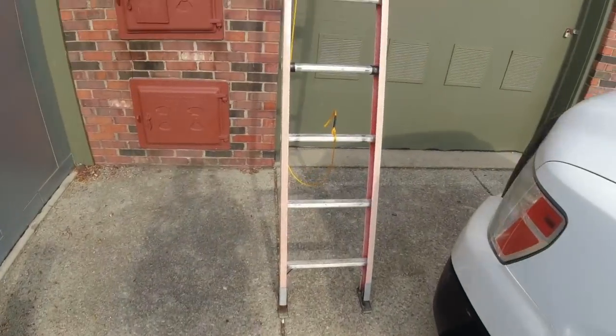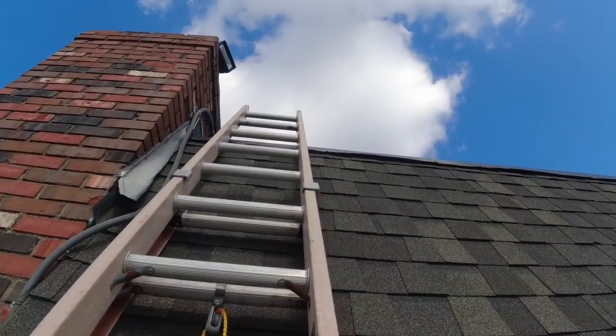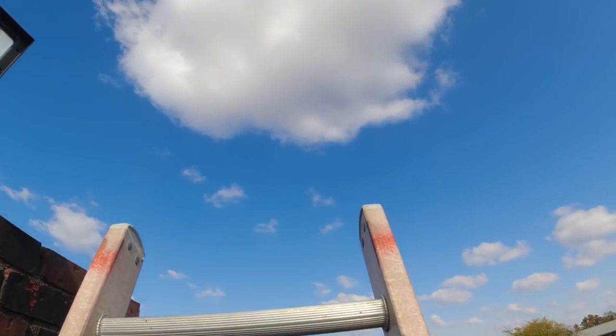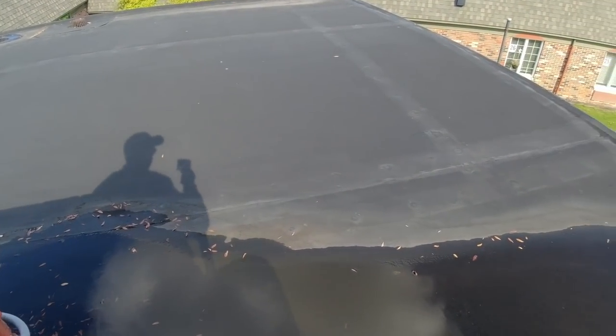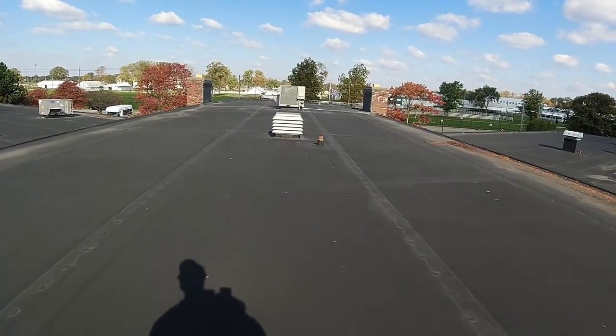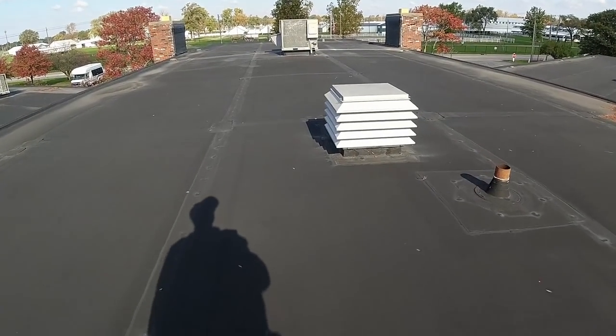Okay, kids, we've got a rooftop unit that does not have power, is what I'm assuming, because the thermostat's blank. I checked power at the thermostat, and we do not have 24 volts. So, should be that package unit right over there. Fairly sure this is the entry into the building. See what we got going on.